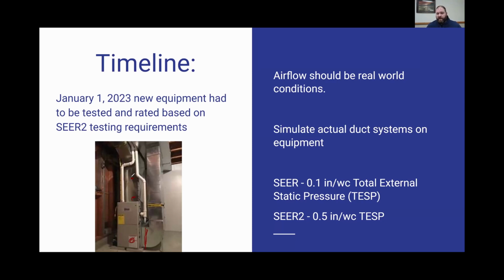Realistically, in homes, a more real world application is a 0.5 total external static pressure. I will let you know that I have seen furnaces running in the field that are in the 0.8 to 1.0, which is outside manufacturer's recommendations, but it's what happens in the real world.